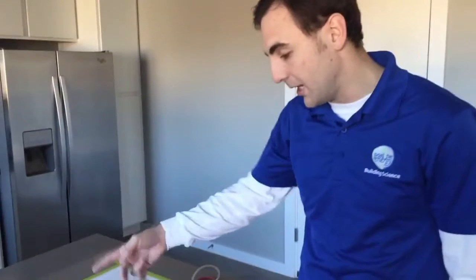I much prefer the balometer as opposed to the anemometer or the pitot tube because it allows me to accurately and quickly measure airflow. There are times where you can't use the balometer. Let's say that you're measuring a fresh air intake and it's on the side of the building and you don't want to climb up to the top. You can then stick this pitot tube in and measure airflow that way. So it just depends on your needs and what you want to accomplish as far as which equipment you'll use.